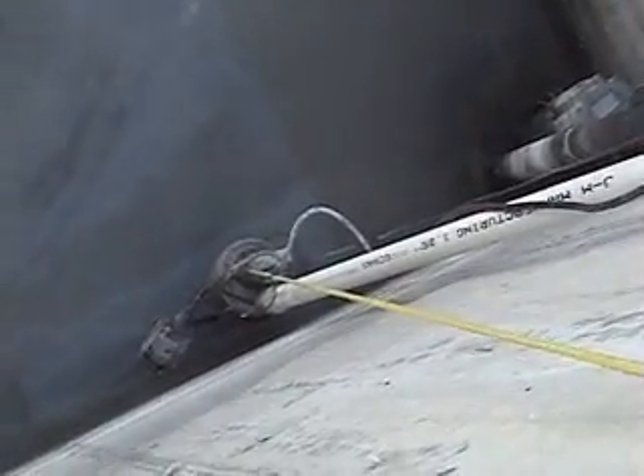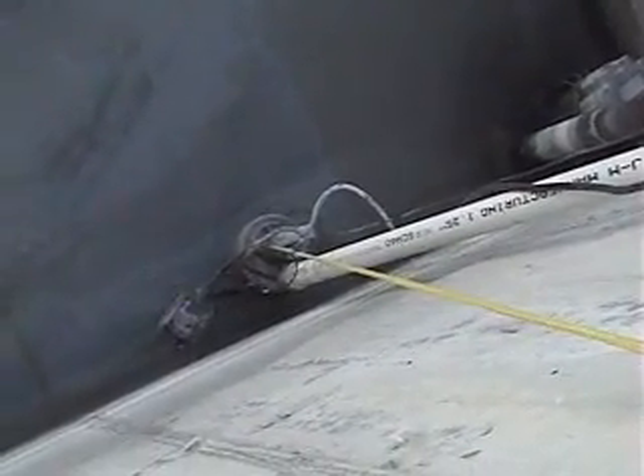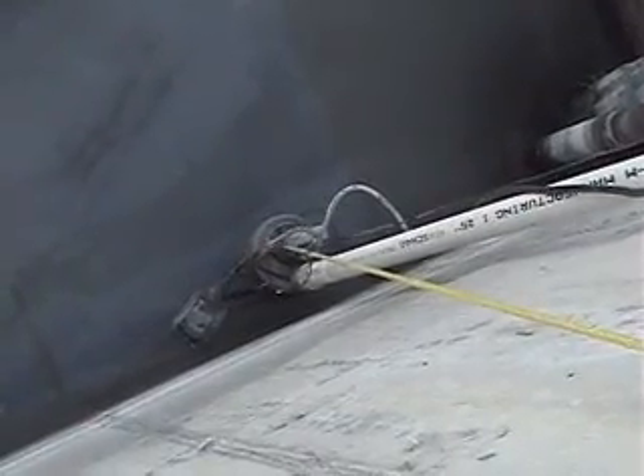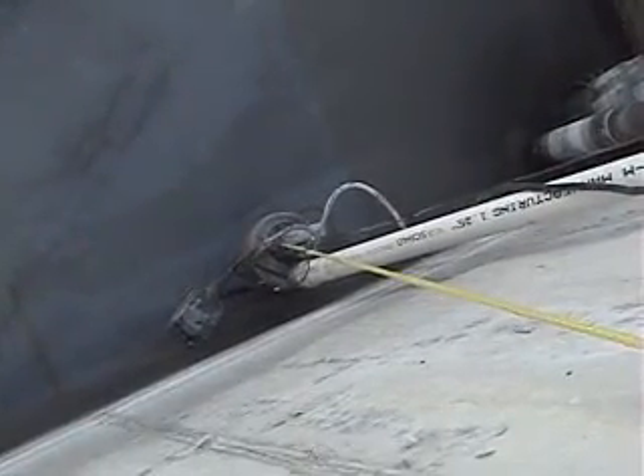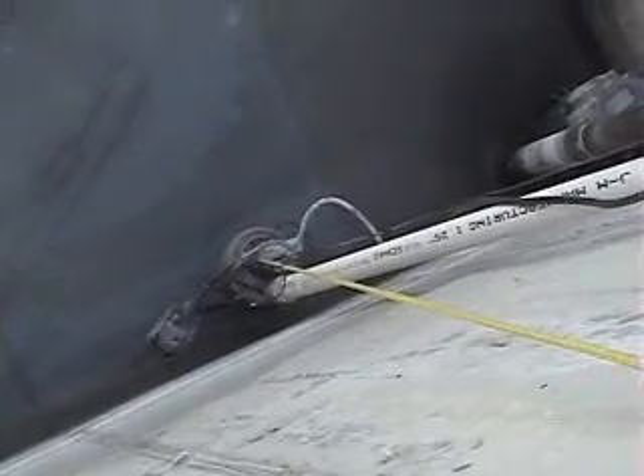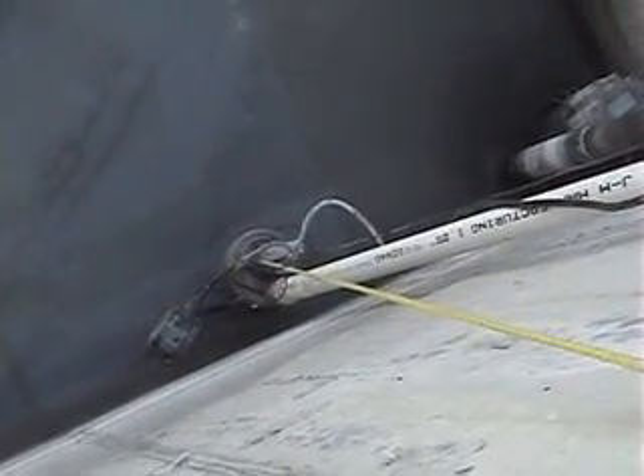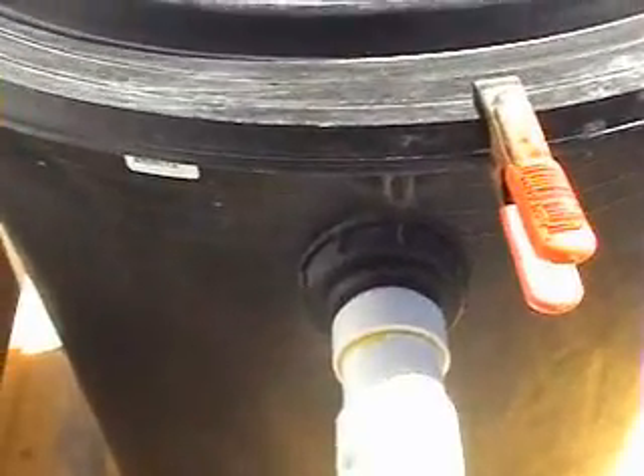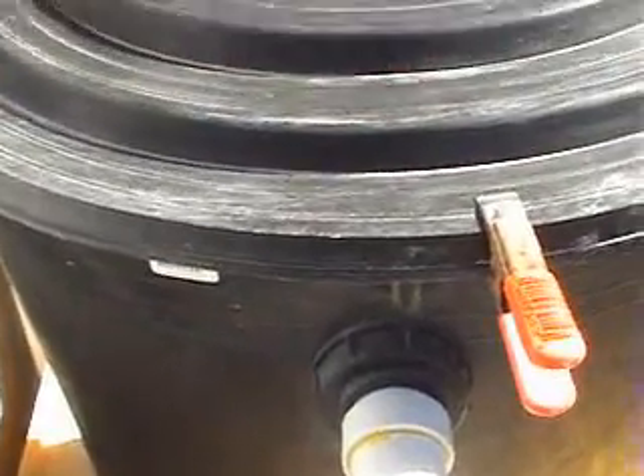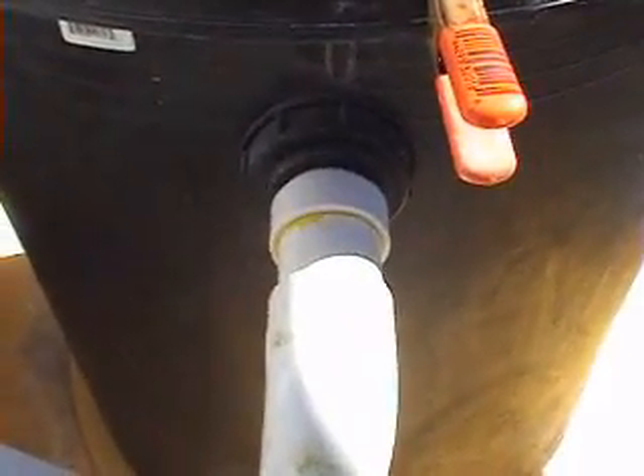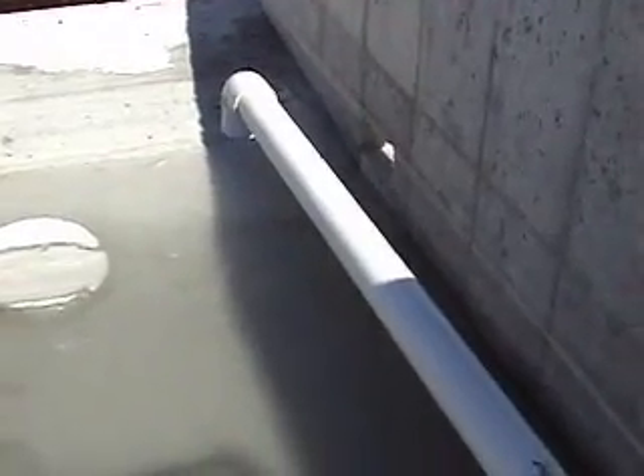What happens again when the system is triggered, when it reaches a high pH, which is your high limit, that set limit, the system will turn on. The relay actually transfers a signal to our pump there, and the water is pumped through the pump up this intake pipe here and is actually brought in to the storage tank, the acid mixing tank here. What happens after the water level rises, it then hits this pipe here, which is our discharge pipe. The water will actually travel down the discharge pipe and back into the sediment basin here.